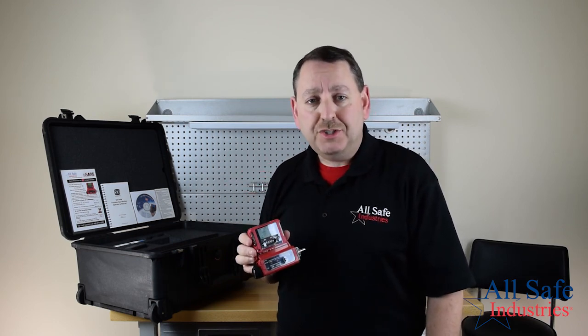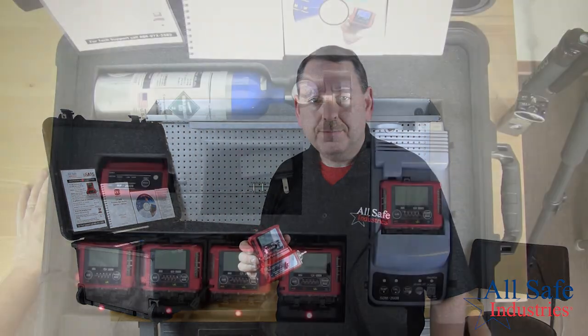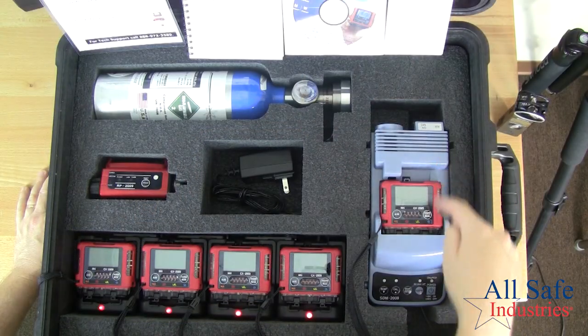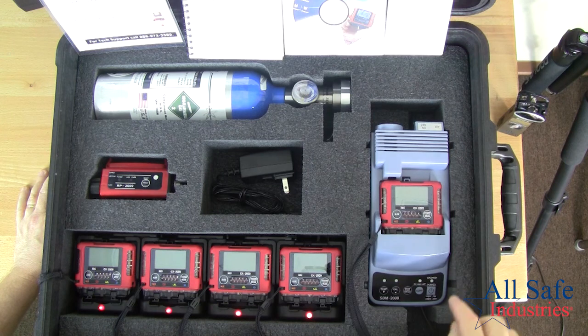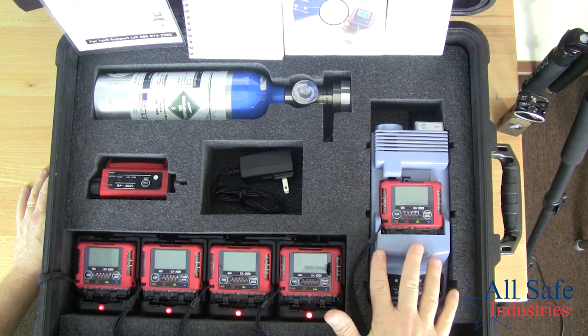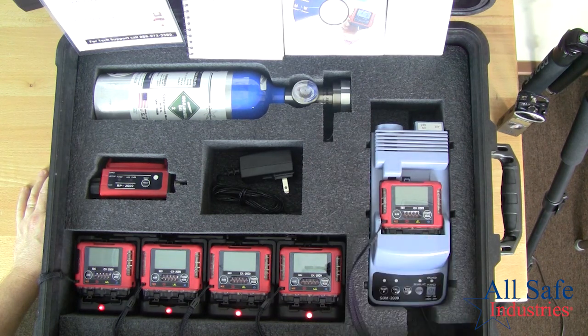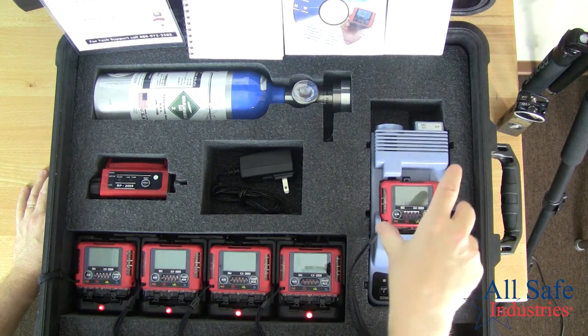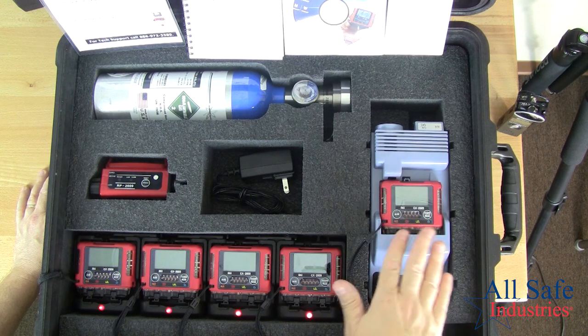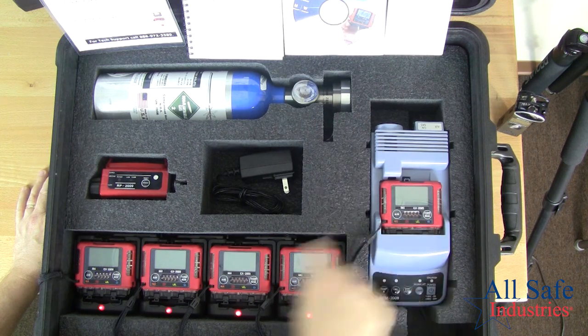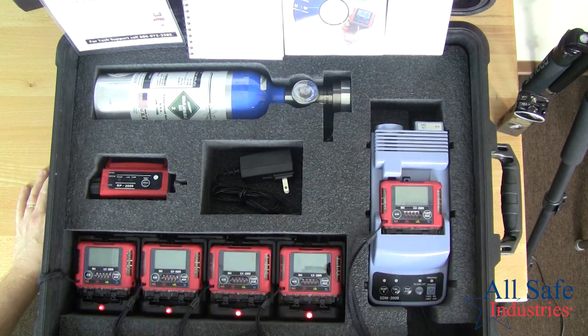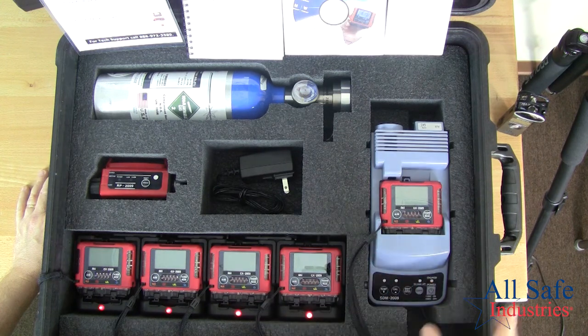There's also a calibration station. Let me show you how that works. Notice in this kit we have a built-in calibration station. The calibration station will automatically bump check and calibrate your meters. It will also charge the batteries, so you'll see the 5th instrument is resting on the cal station so that it can charge, and then I can cycle each meter over to the cal station so that I can do the bump checks of the calibration.